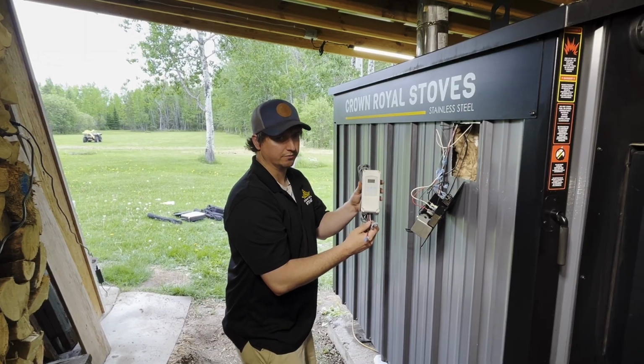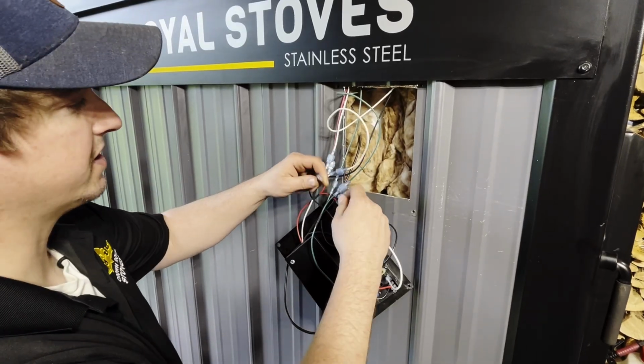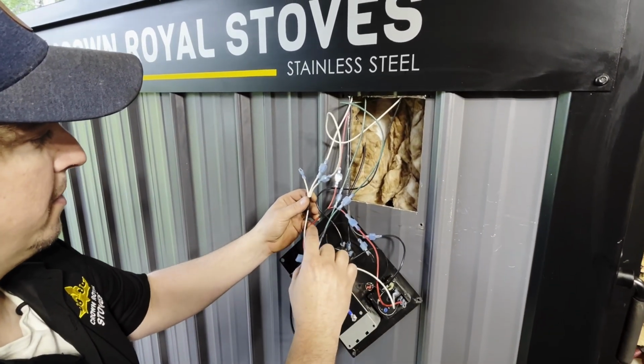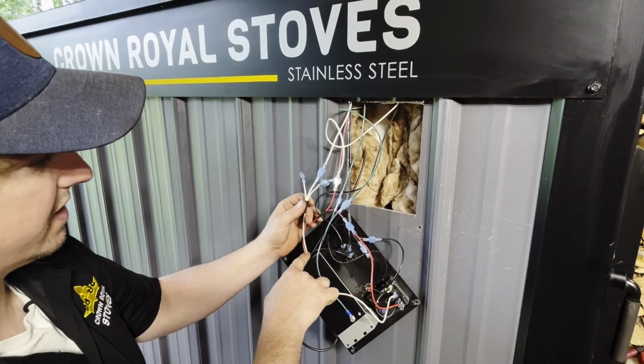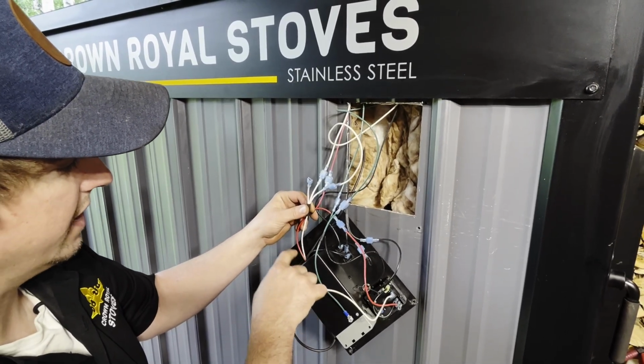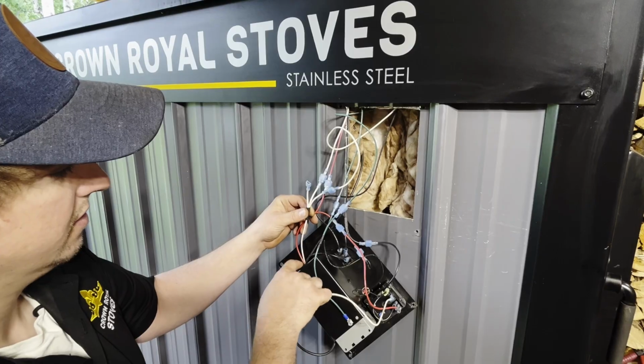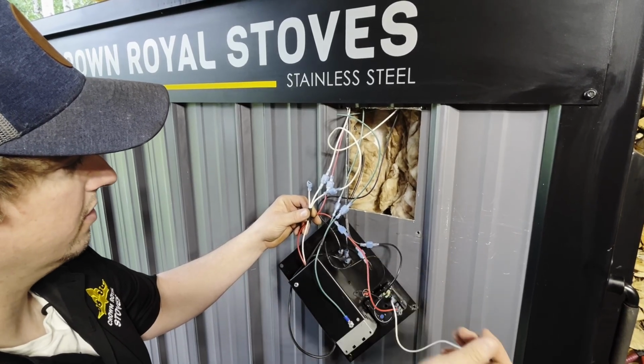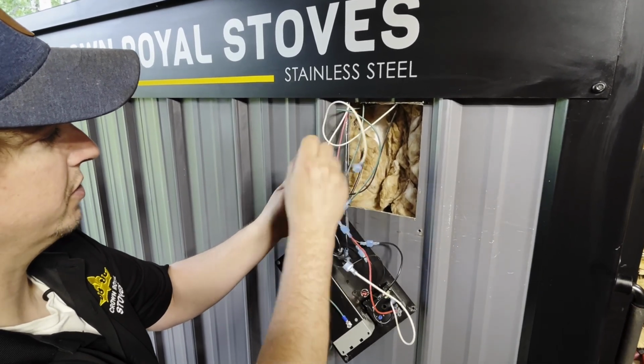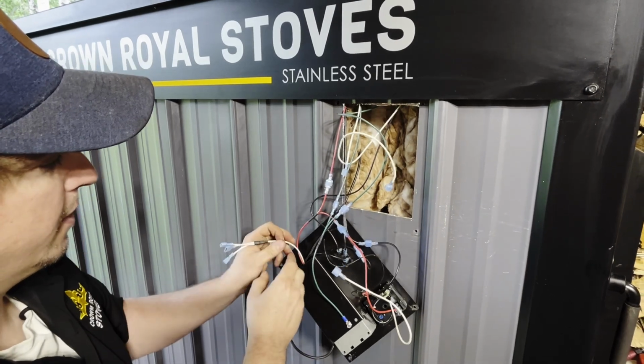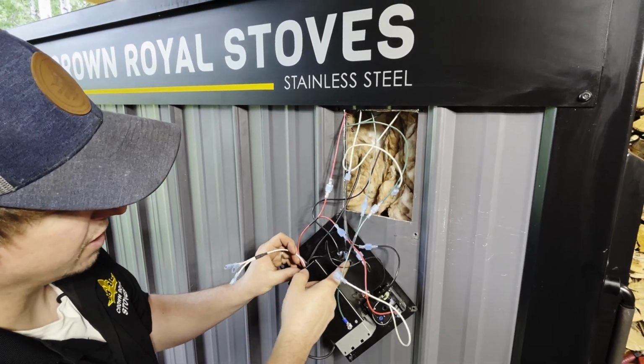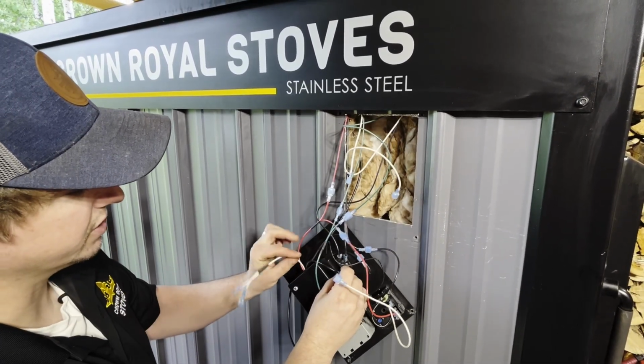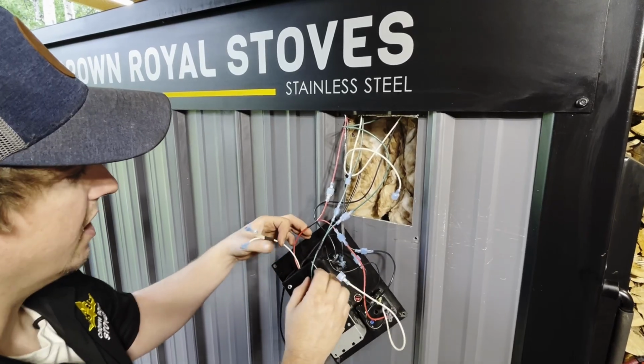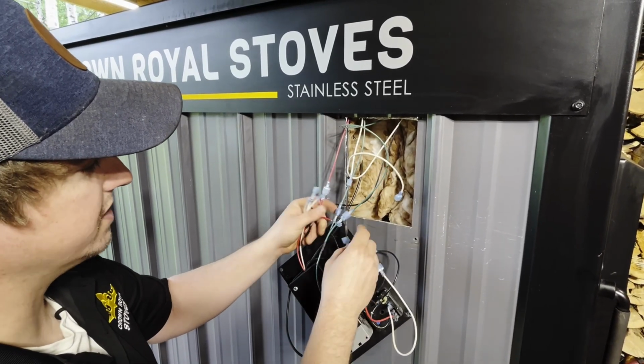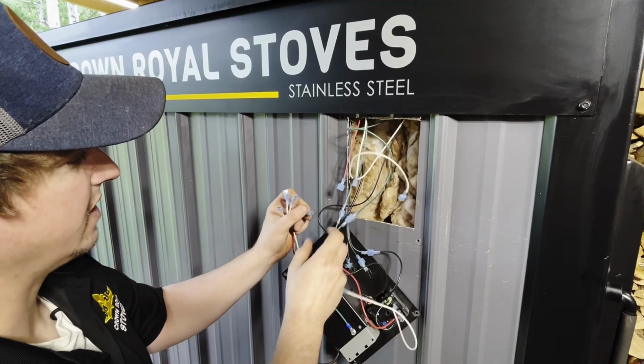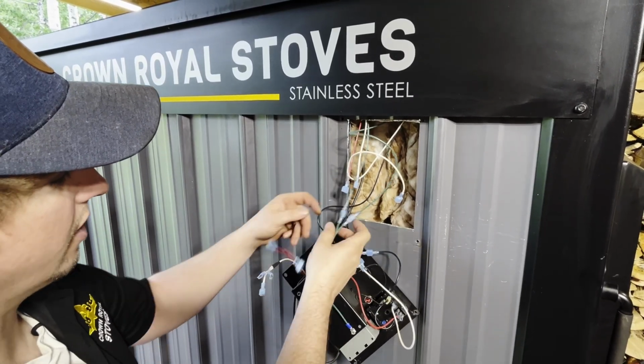Okay, I'm going to start disconnecting these pigtails. I'm only going to be disconnecting the wires that are connected to the Aquastat, so we're going to take note. All of the whites are pretty self-explanatory. This black wire does come down to the 3-way switch, so there's one to the 3-way switch, and then we've got 2 reds, and we've also got our ground wires.